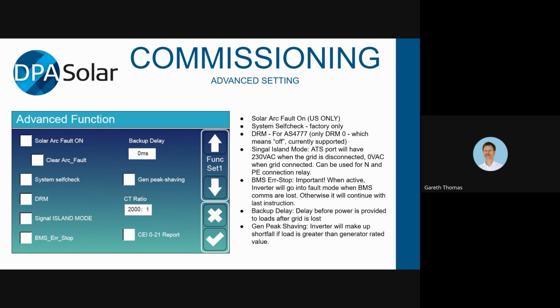BMS Err-Stop, this is another important one. So when active, the inverter will go into fault mode when BMS comms are lost. Otherwise, it will continue with the last instruction. So what that means is if you pull the BMS cable out of the inverter, if you don't have this on, it will just keep going, but it will just assume whatever the BMS last told it to. So if it said keep charging, it will just keep charging. If you have this switched on and you pull the cable out, it will then go into error and switch off. It sounds like you might not want that because you might want it to continue in unmanaged mode, but it's not what it's set up for because it doesn't have fallback voltage settings. It's just going to keep going. So you want to have BMS error stop switched on.